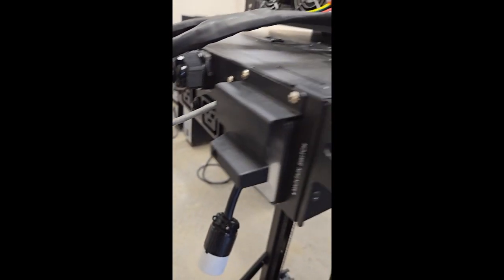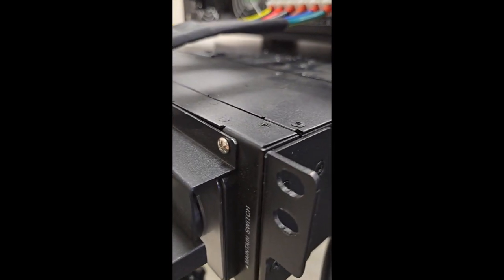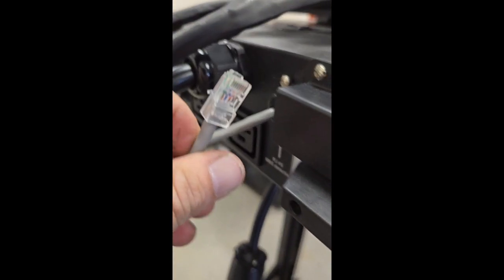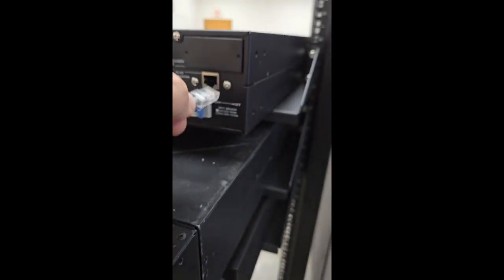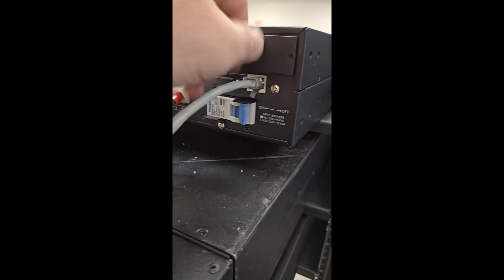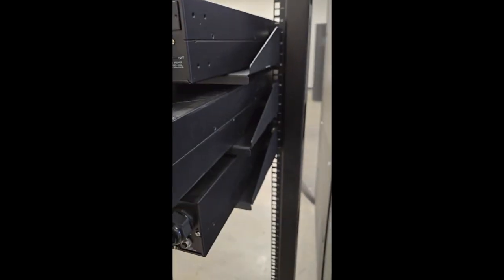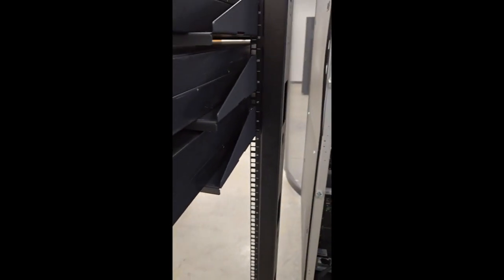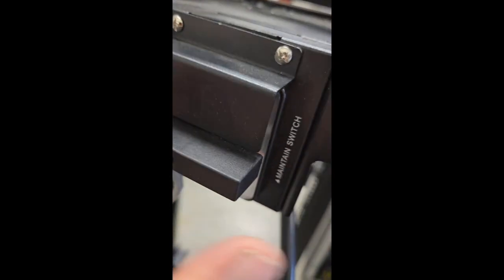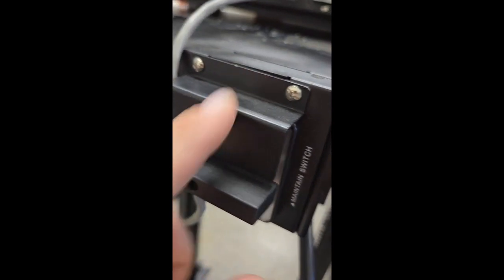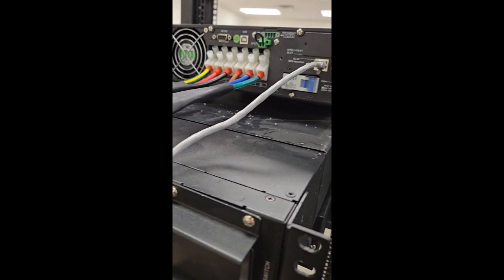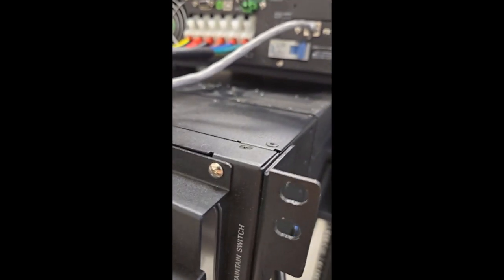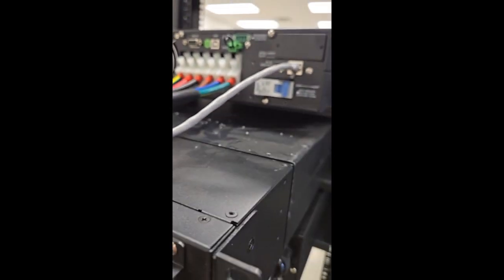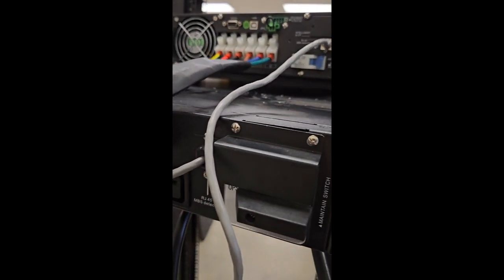One more connection from the bypass to the UPS. This connector is important, the little RJ45 connector. This isn't really communication, but plug it into the back of the UPS. What that actually does is, there's a micro switch behind this plate. So when the plate is removed, the micro switch is released, and it actually sends the UPS into a mode of static bypass to avoid backfeeding the inverter of the UPS.